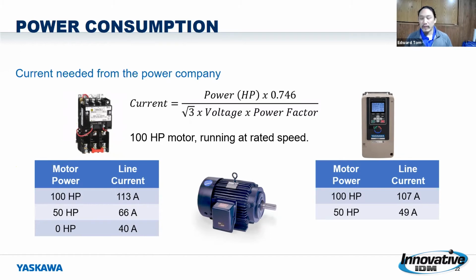Well, there's going to be your reactive power that's out there. The energies, the current and voltage that's needed, ultimately the power that's going to be needed to get that motor spinning. I'm going to still need to draw 40 amps regardless at this point. Well, what about with a VFD? The motor's running, but there's no torque being produced on there. It's just spinning at this point. Well, the amount of current you're going to need on the input side is going to be pretty close to zero. It's going to be, in this case, about 1 amp. So big difference when it comes to the different amount of loading that you're putting on there.